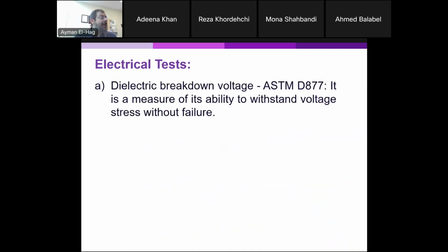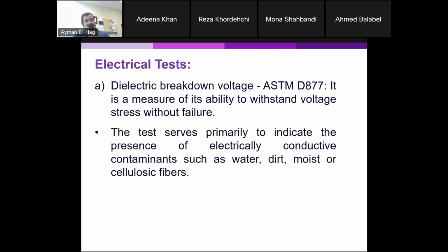Electrical test, the breakdown test, this is the standard test. And it's done as per the ASTM standard D877. I mean, all the standards I mentioned to you here, there are some counterpart standards in IEC, but I'm just using the ASTM here because this is what is used in North America. Now, in that test, basically, you try to see how much withstand voltage the oil can take. So basically, you apply a voltage until you have a breakdown, and you want to see what is the strength of the transformer oil, how much voltage it can take.